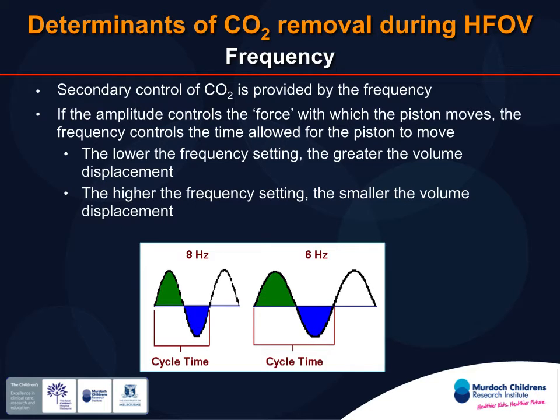And that can be quite important and needs to be considered in your strategies, particularly if you have a condition of gas trapping. If you have a condition where getting gas out of the lung is a problem, not only is your absolute frequency going to be important, but allowing the lung enough time to deflate between each cycle will be important too. So I tend to avoid I:E ratios of 1-to-1 if I have conditions of gas trapping. There's a lot of debate, and it happens a lot in Australia, between a 1-to-1 and 1-to-2 ratio in terms of injury, shear force stresses on the lungs, and modelling of lung injury. I think probably in the HFOV baby, it's somewhat irrelevant whether it's 1-to-2 or 1-to-1 because of the sort of lung disease you're treating. It may be relevant for some of the actual specific devices.